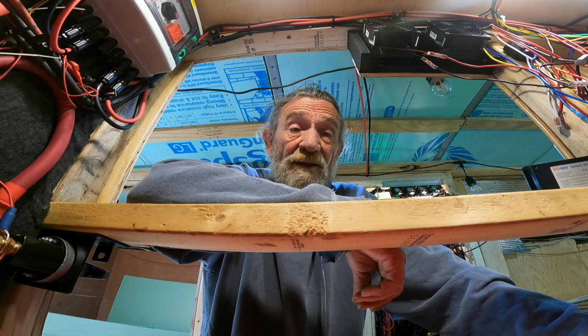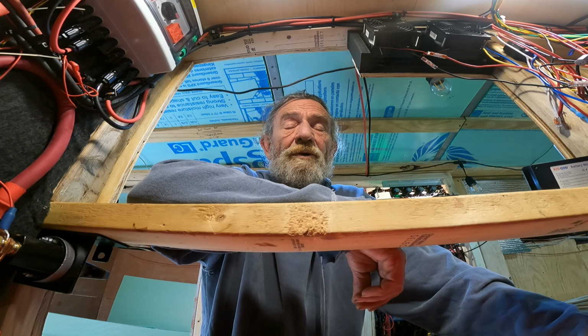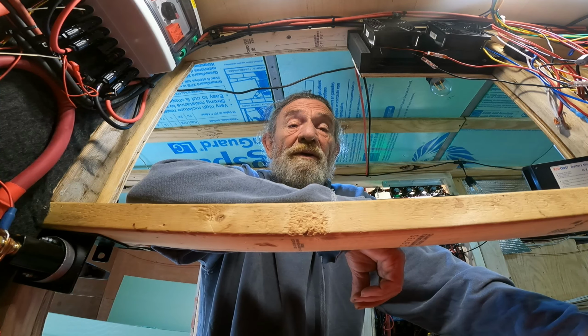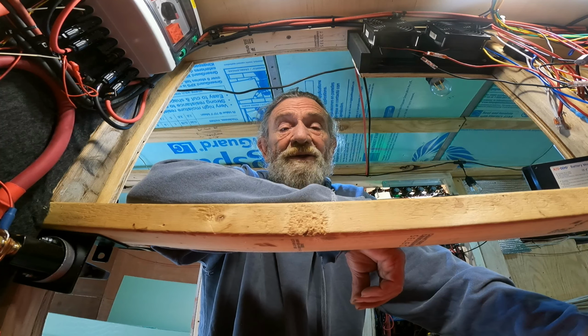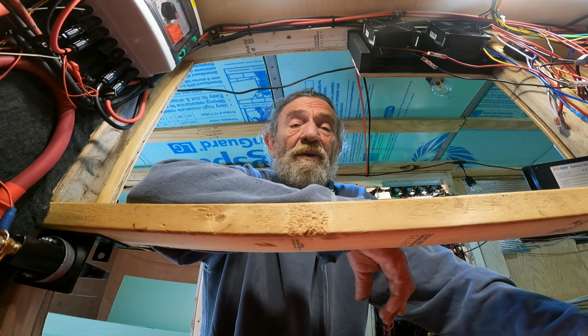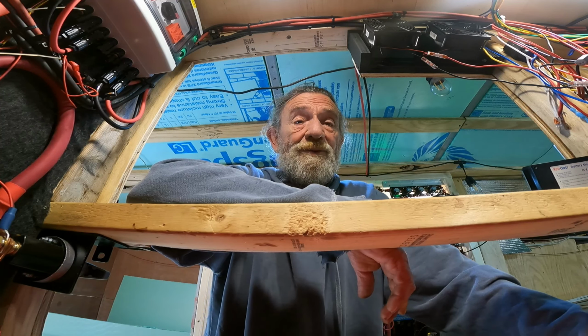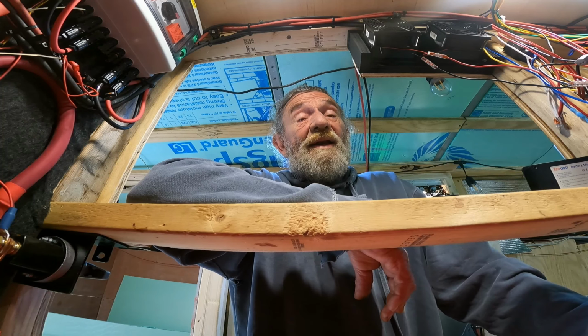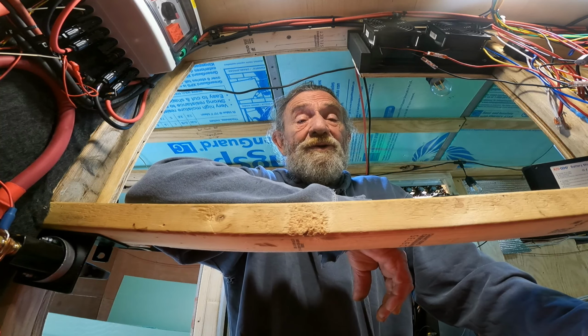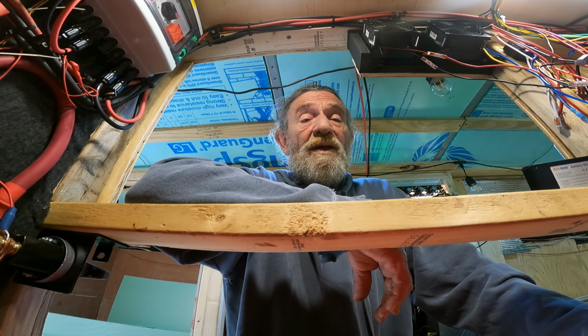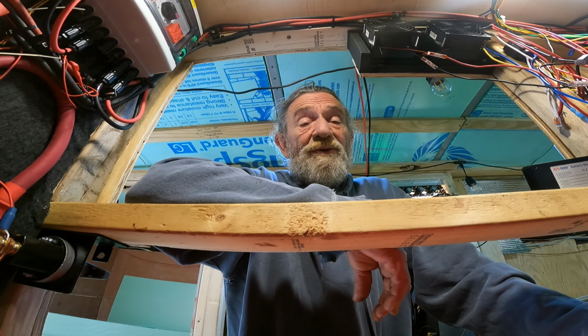So VE CAN requires terminations on both ends. VE bus does not - it's, for lack of a better way of putting it, like standard Ethernet cables. So I had everything tied together in a single string running off of VE CAN going into the Cerbo GX, and both ends terminated.